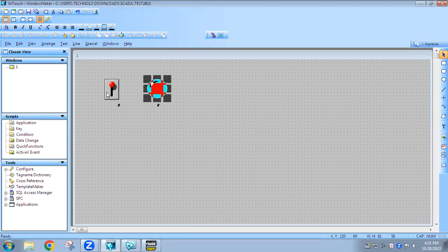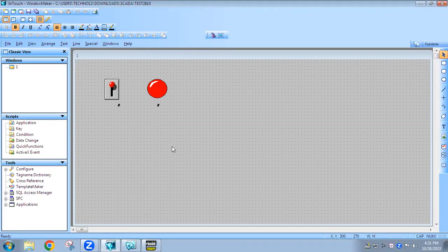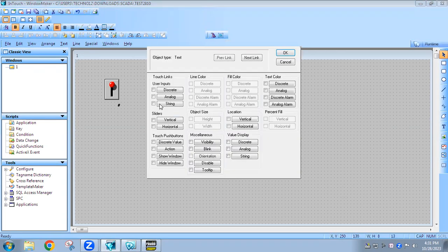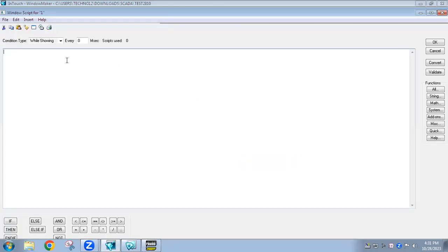When connecting with PLC, we have to give different tag names, and it will only respond when connected to the PLC — during simulation testing it won't work. So to support different tag names during the testing period, they have provided the scripting language. In your window, if you right-click you can see 'Window Script' where you can write coding. It uses basics from C language — if, then, else, else-if, end-if, as well as logic operators like AND, OR, NOT.